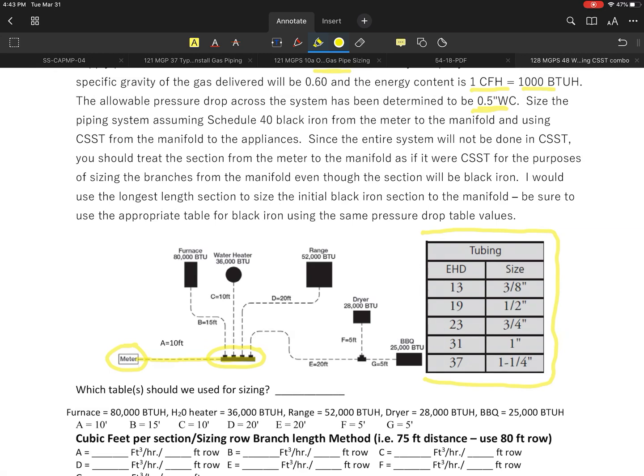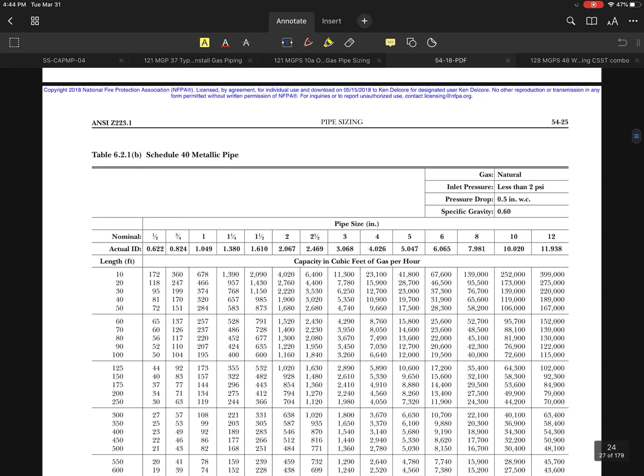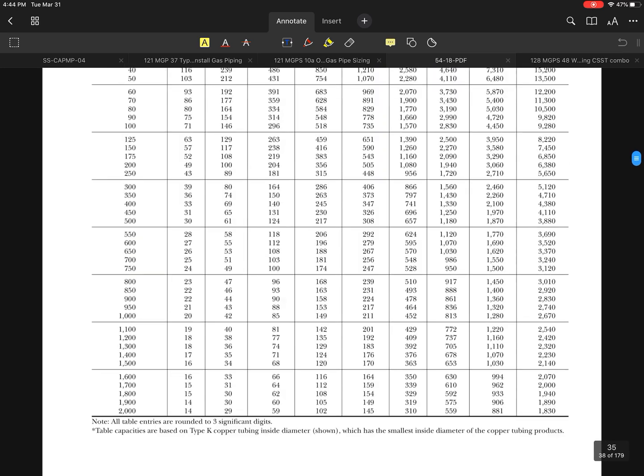Make sure you follow the correct tables and you understand what their diameter is when you're applying this type of tubing. My general focus is going to be on the sizing for this. For example, on a 3/8" tubing, they're going to have an equivalent hydraulic diameter of 13, half inch is 19, 23 for 3/4", 31 is 1 inch, and then 37 is 1-1/4".